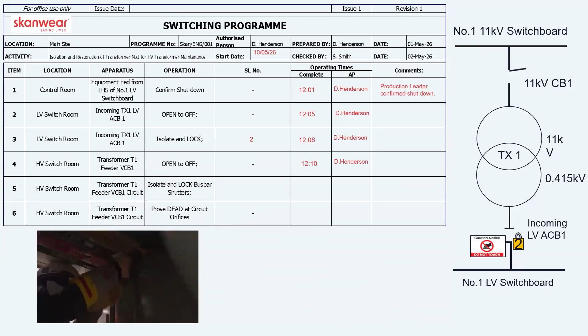So we're still on line 5 here. So we've removed the circuit breaker, and we're now going to lock the busbar shutters. So those busbar shutters underneath there are still live 11 kV. So we'll now apply a lock and a danger sign or a caution, depending on what your safety program says, so we can't actually come into contact with the live 11 kV.